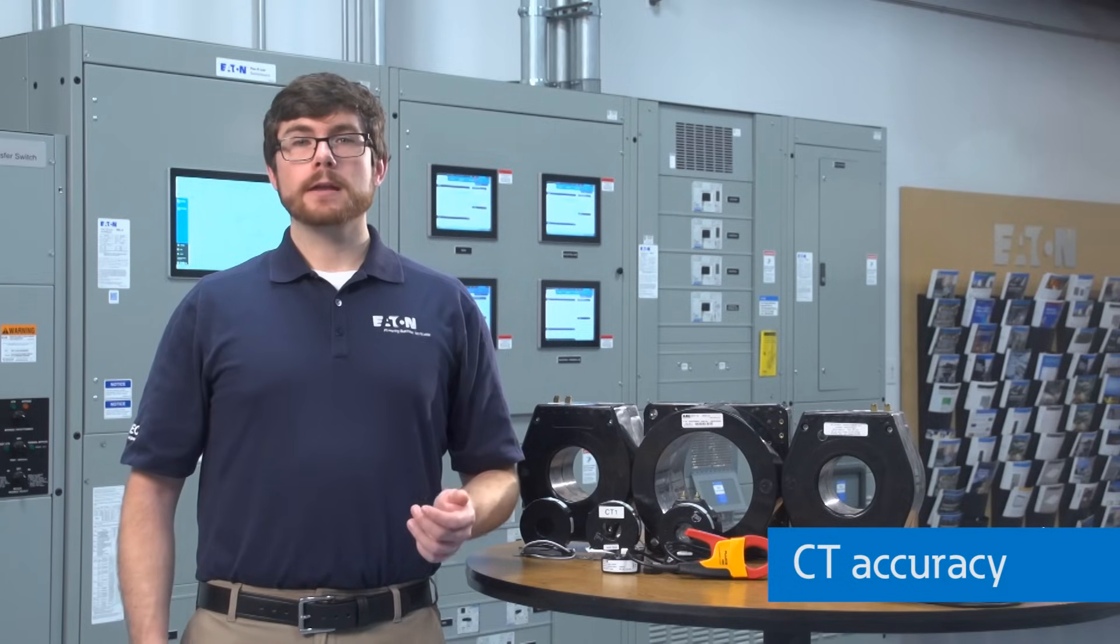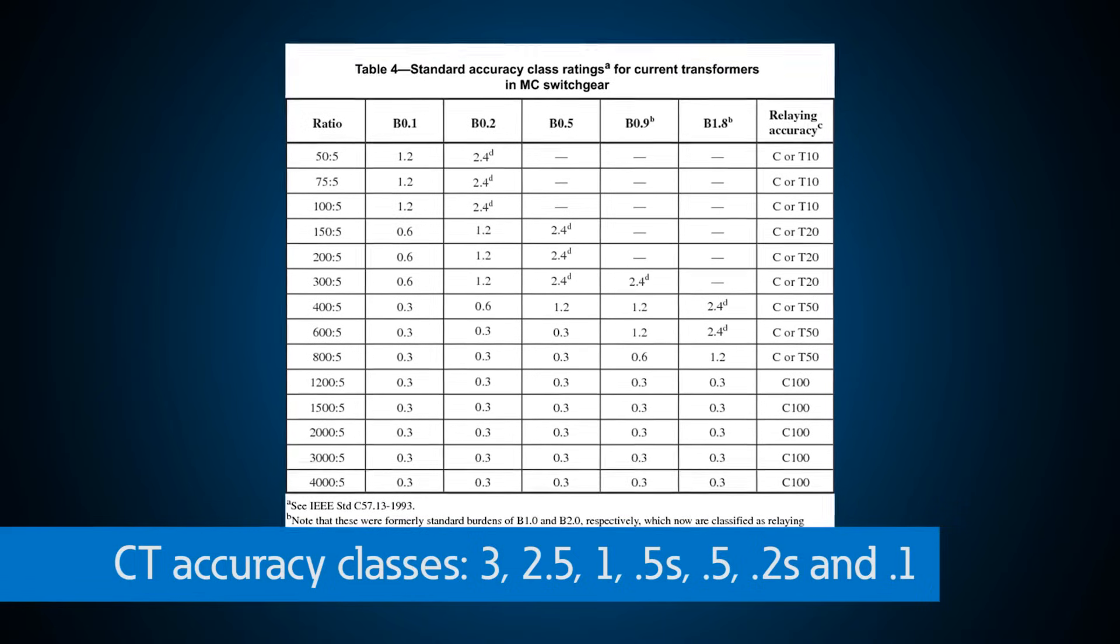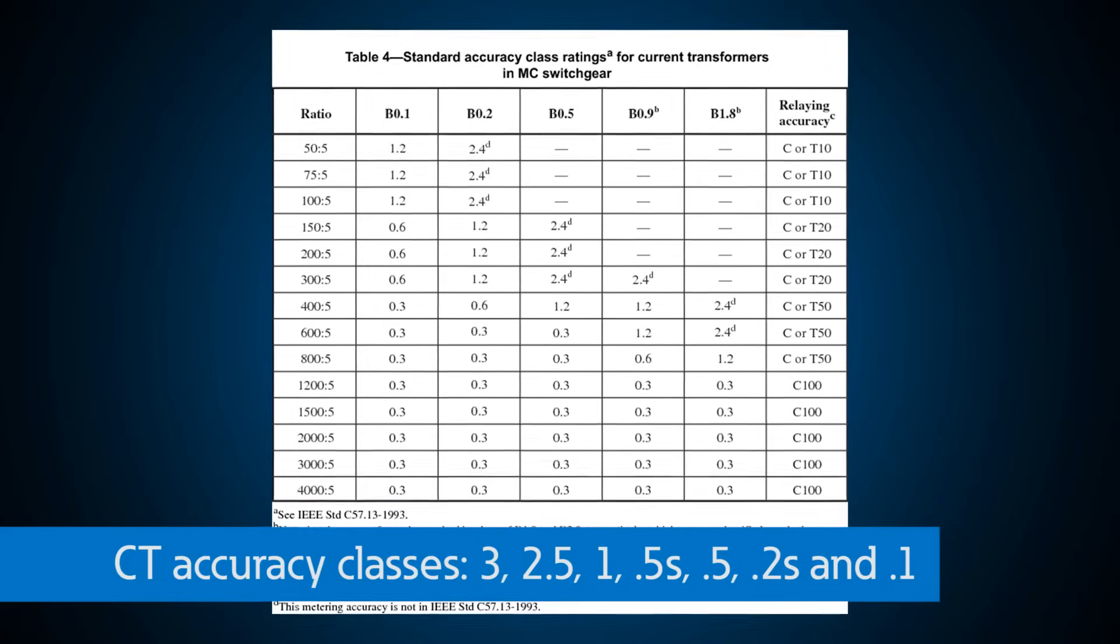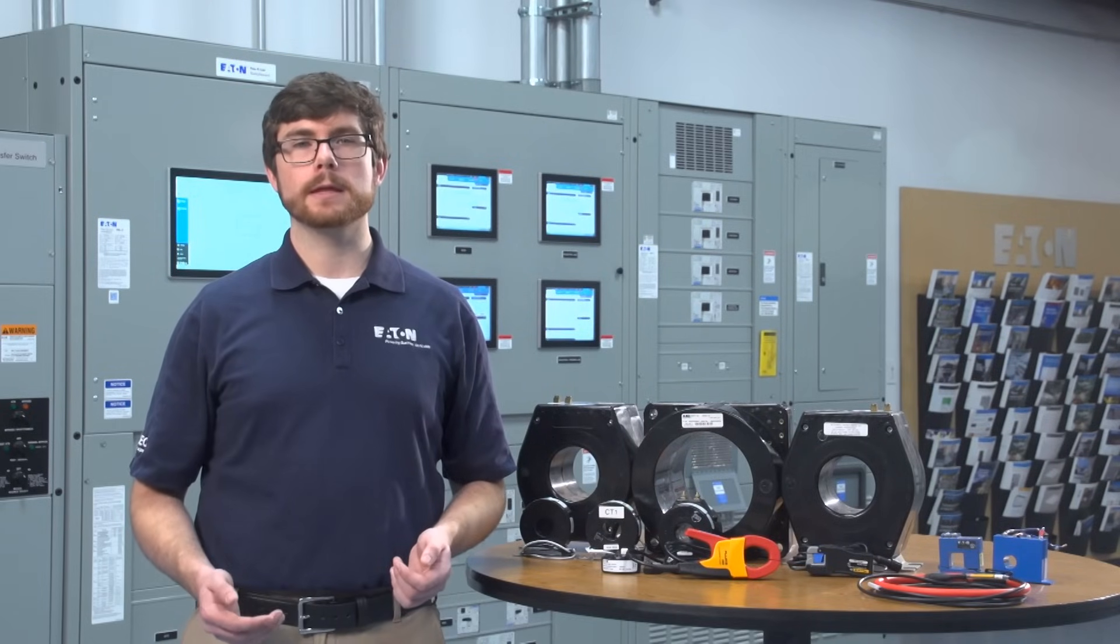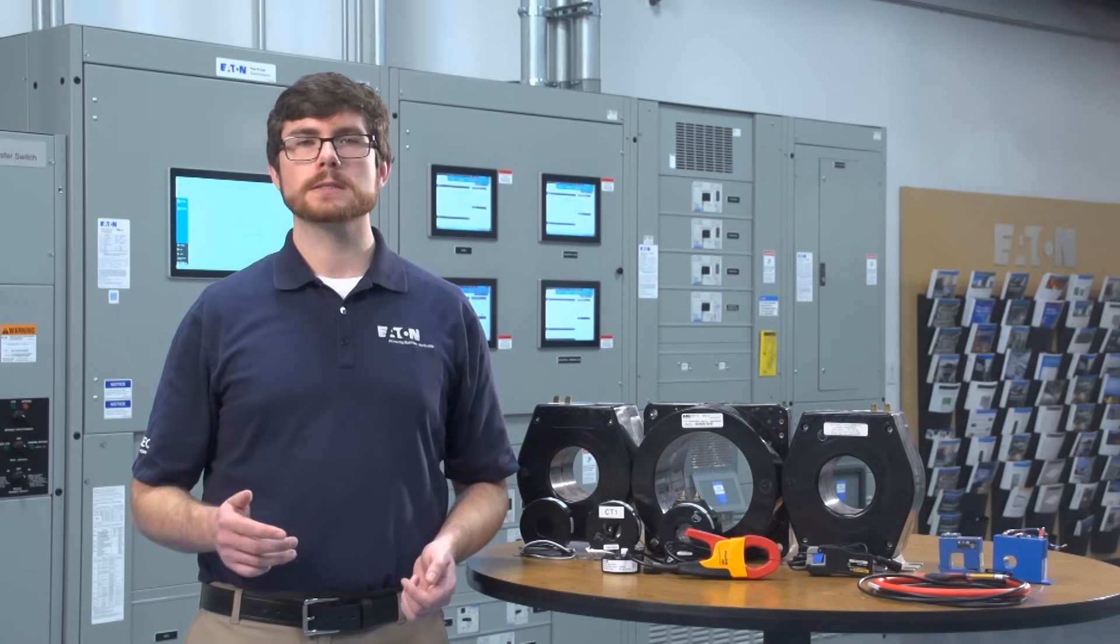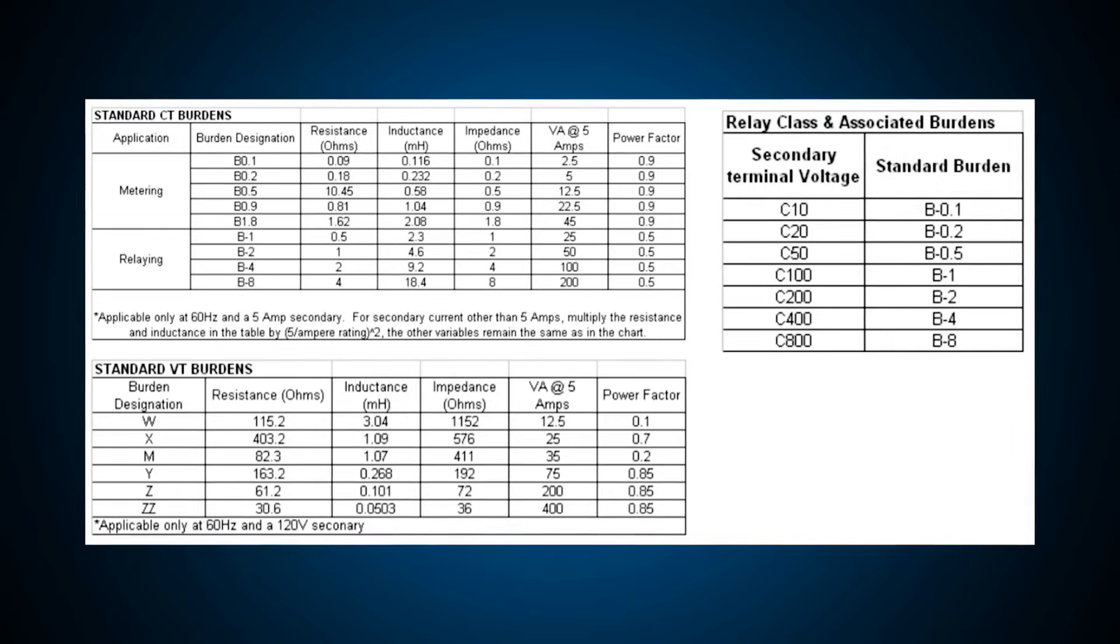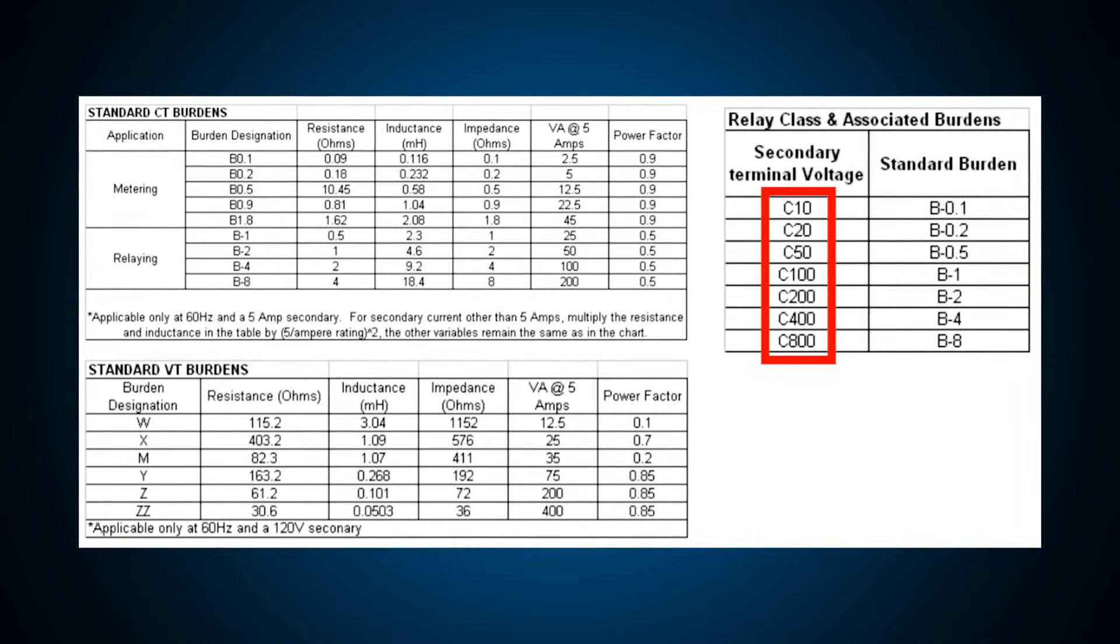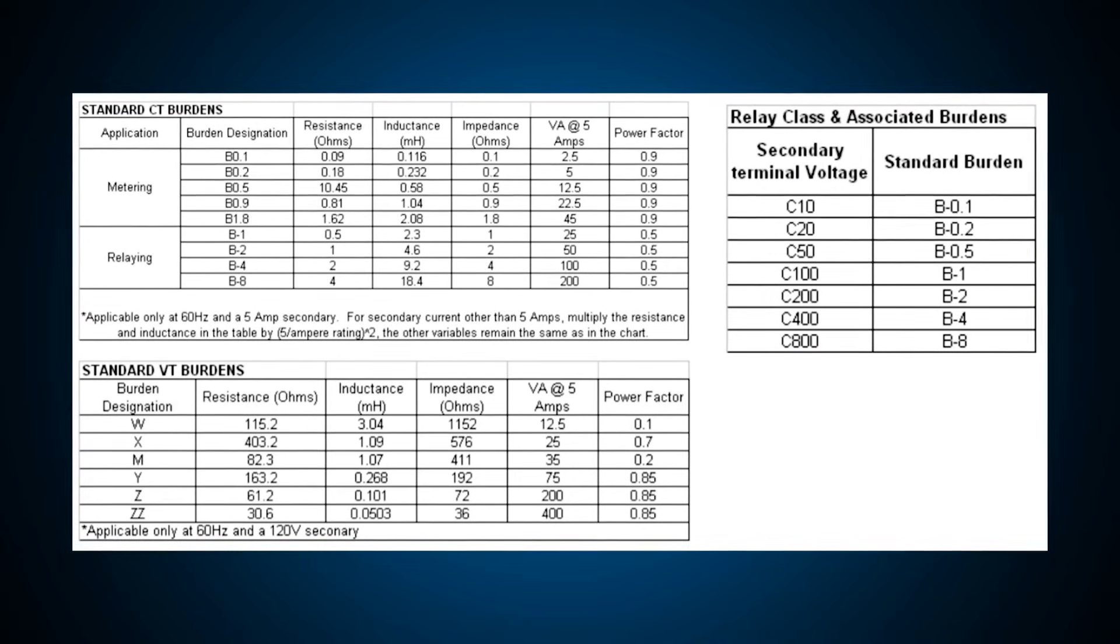CTs come in a variety of accuracy classes. For example, the ratio of primary to secondary current error of a class 1 CT is 1% at rated current. A 0.5 rated CT is 0.5% or less. The accuracy of these devices is very important for protective relaying and metering. They have specific requirements for overload currents in excess of the normal rating to ensure accurate performance of the relays during system faults. A current transformer can have a range of ratings from C10 to C800, which is related to the secondary winding output voltage capabilities and VA rating of the CT.